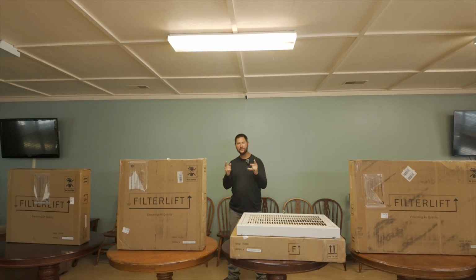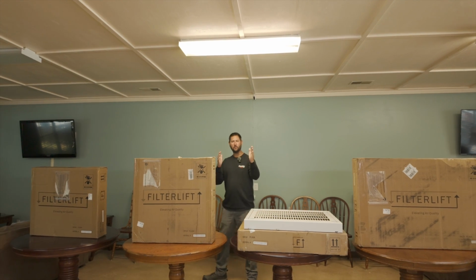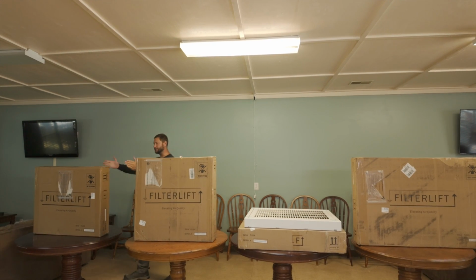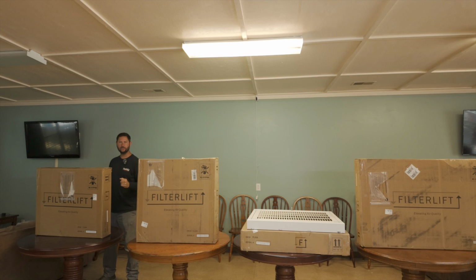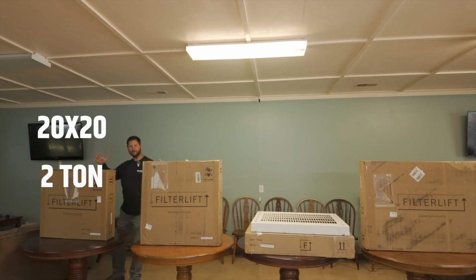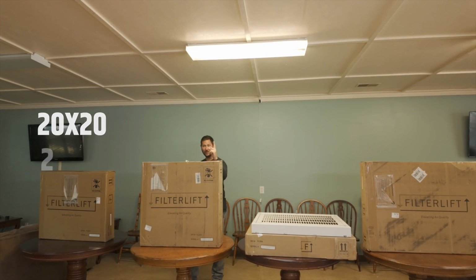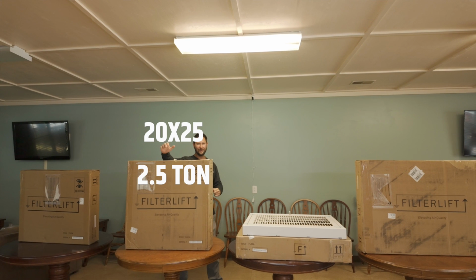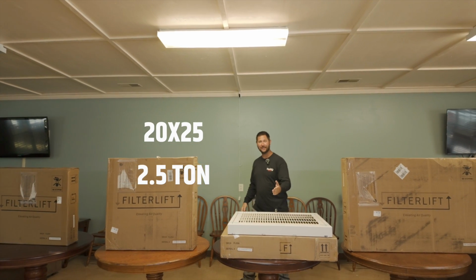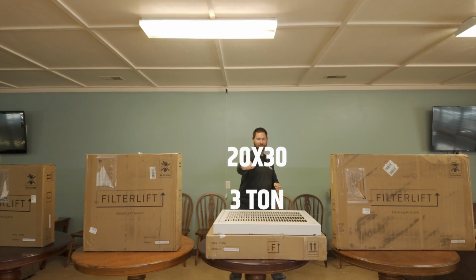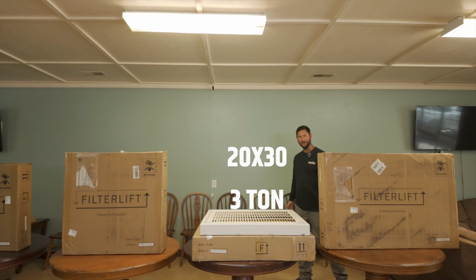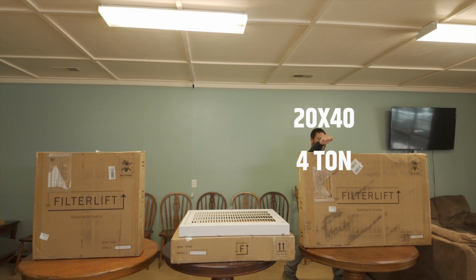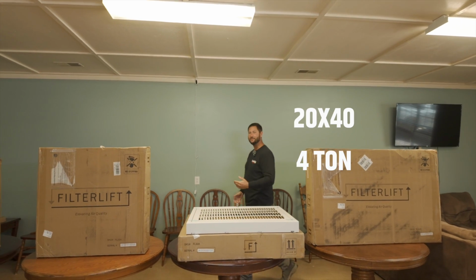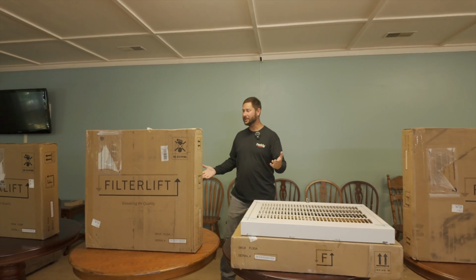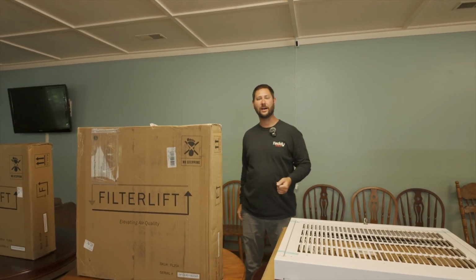Now let's go over each residential size and what grill you need. For the 20 by 20, you can do a 2-ton. For the 20 by 25, you need a 2.5-ton. For the 20 by 30, you can do a 3-ton. For the 20 by 40, you can do a 4-ton. And then if you got a 5-ton unit, you can do 2 20 by 25s.